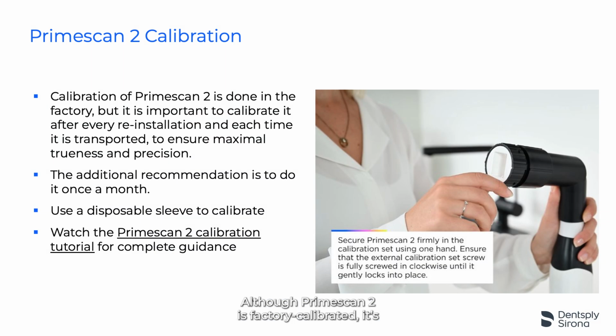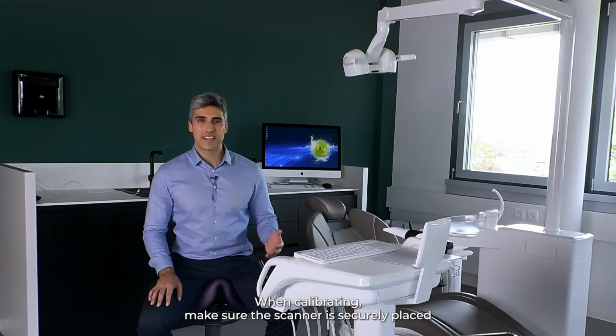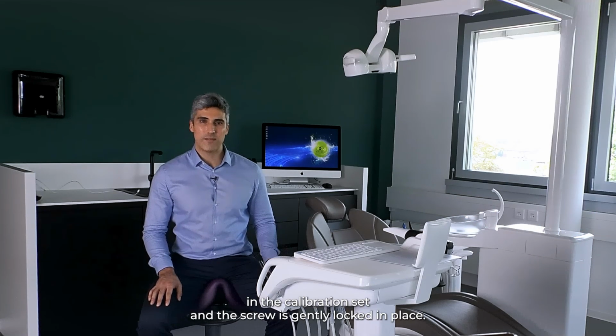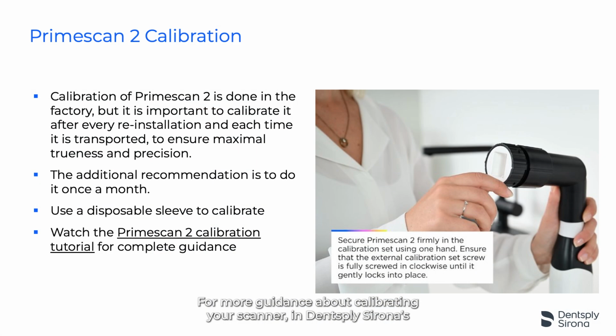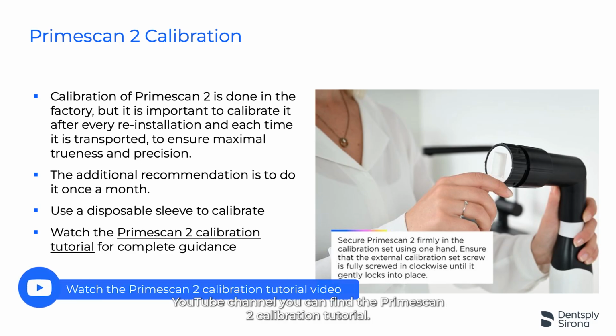Although Primescan 2 is factory calibrated, it's essential to recalibrate after any reinstallation or transport outside of the practice, not from operatory to operatory room. We also recommend monthly calibration as a best practice. When calibrating, make sure the scanner is securely placed in the calibration set and the screw is gently locked in place. For more guidance about calibrating your scanner, on Dentsply Sirona's YouTube channel, you can find the Primescan 2 calibration tutorial.